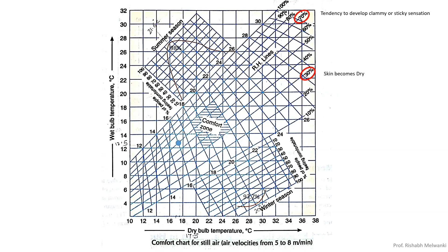And if you closely study the previous chart, you will find that for several combinations of wet bulb temperature, dry bulb temperature and relative humidity, you can get same effective temperature. So here you can see this effective temperature of 16 degrees Celsius. At this location, you will have different dry bulb temperature, different wet bulb temperature and different RH, but effective temperature is same. This point we have already discussed, summer condition and winter condition on the chart itself.